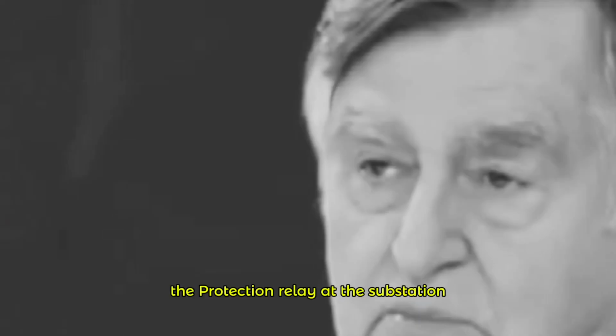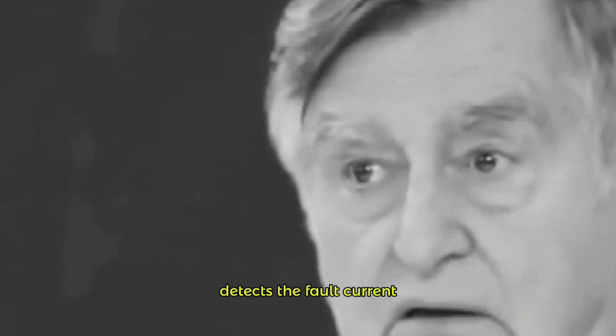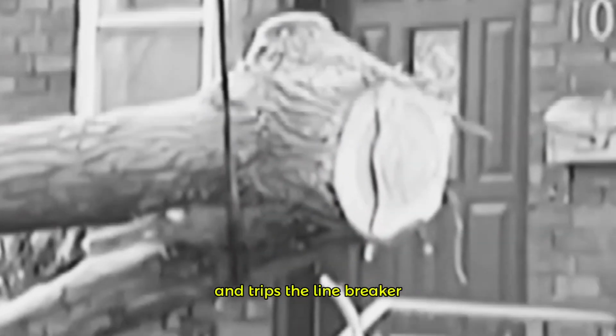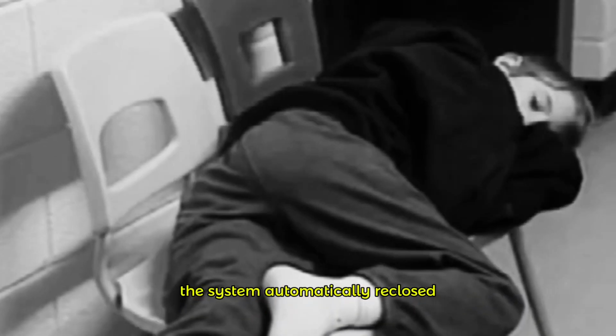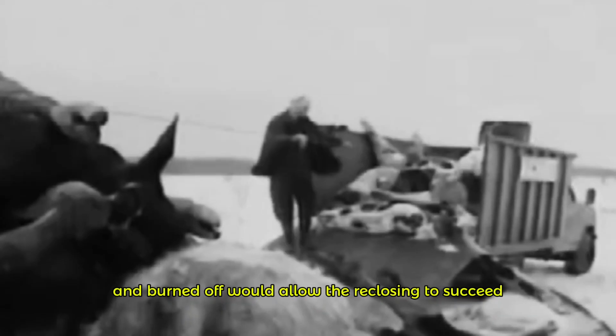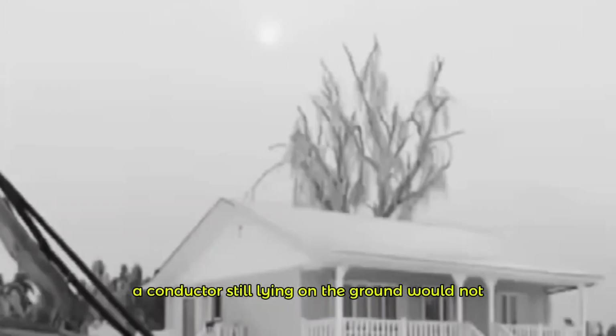The protection relay at the substation detects the fault current and trips the line breaker. On a modern digital relay system, that trip happens in under 100 milliseconds. On older electromechanical equipment, it takes 200 to 300 milliseconds. Say after the trip, the system automatically reclosed, sent voltage back onto the line to test whether the fault had cleared. A tree branch that briefly contacted the conductor and burned off would allow the reclose to succeed. A conductor still lying on the ground would not.